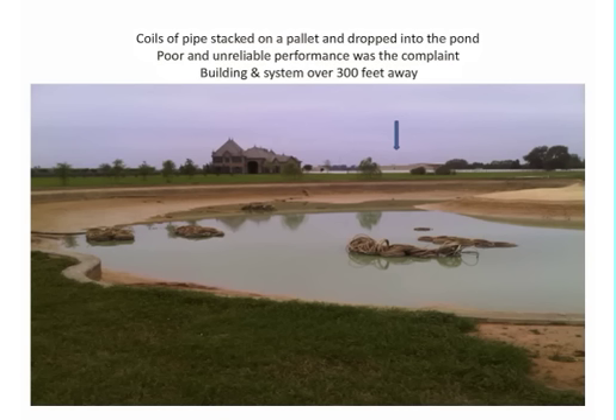They were significantly far away. One of the barns had 1,560 feet of 1.25 inch pipe. That's not the pond loop pipe, because that stuff was 1-inch pipe. But that is a long distance in supply and return pipe. Honestly, you probably should have just buried a ground loop. This was not a good application because of the distance between the particular barns and the pond loop. I want to emphasize that is a consideration not to be ignored.